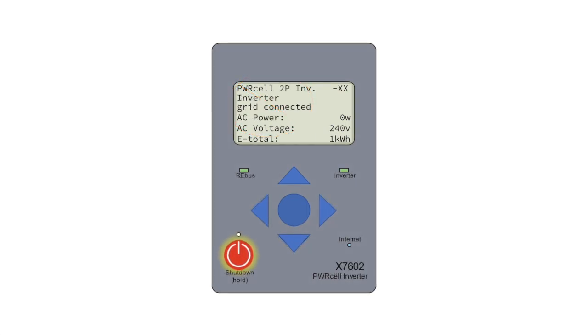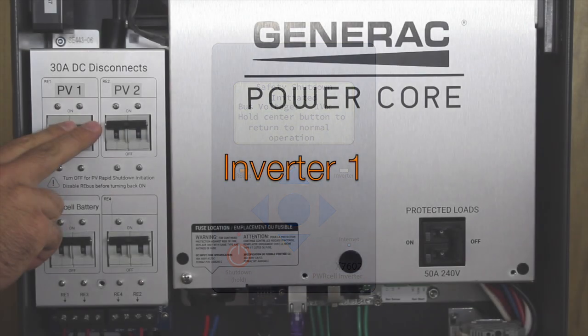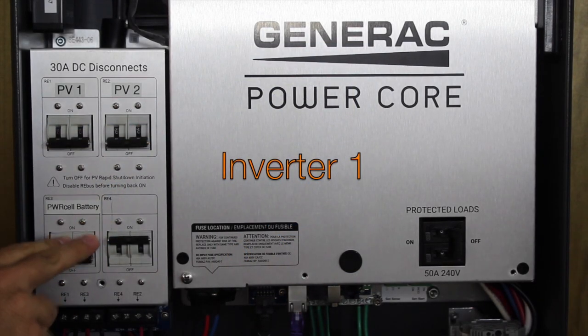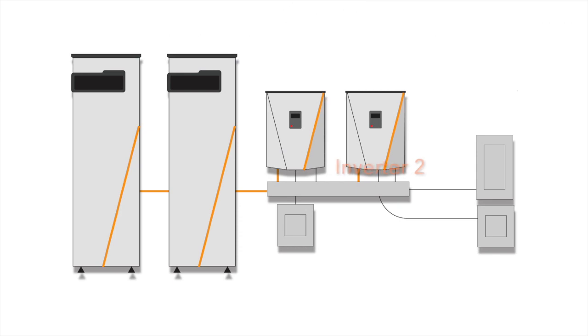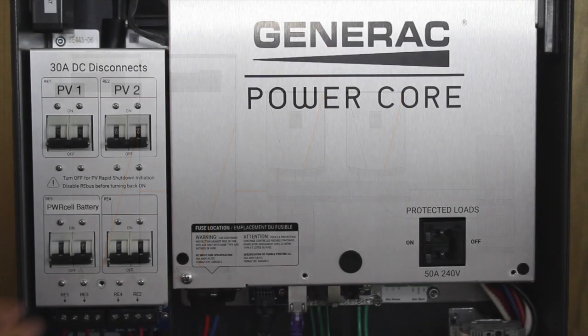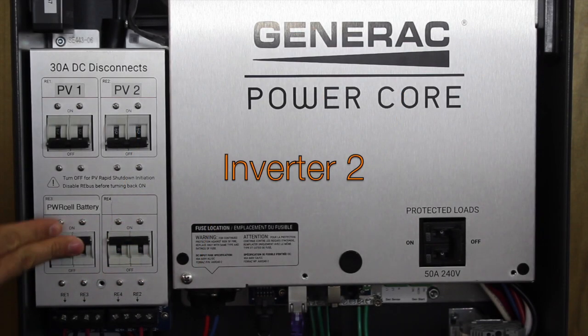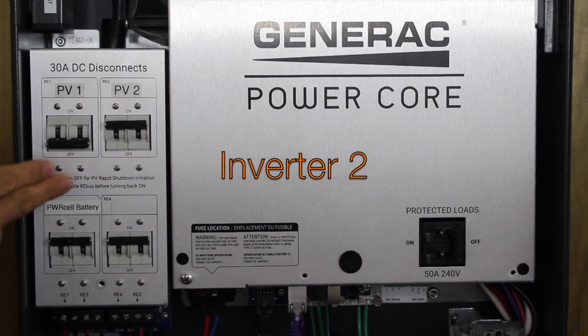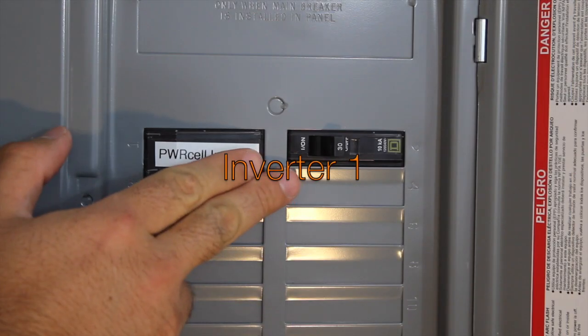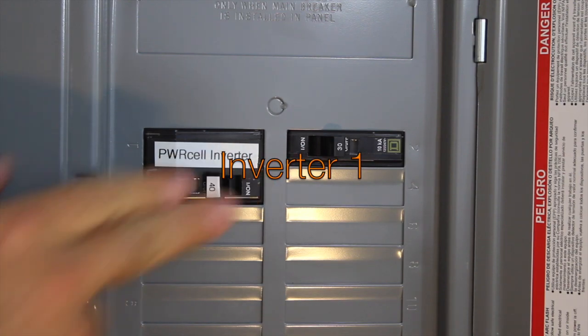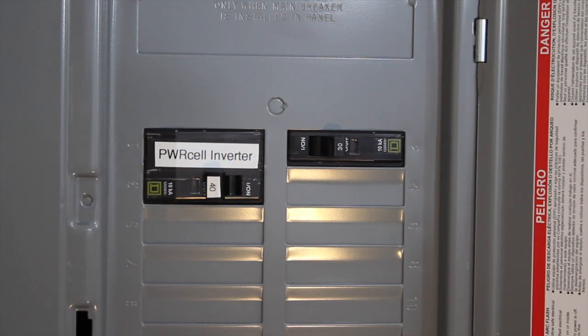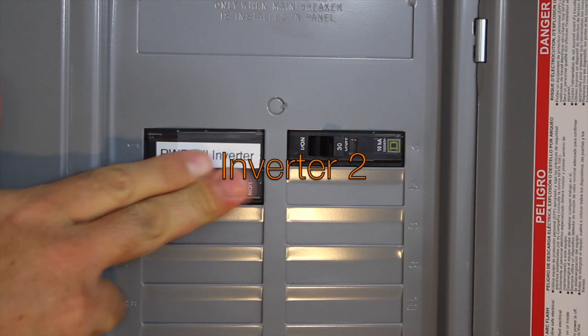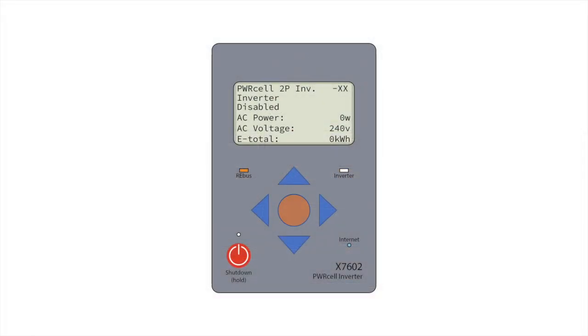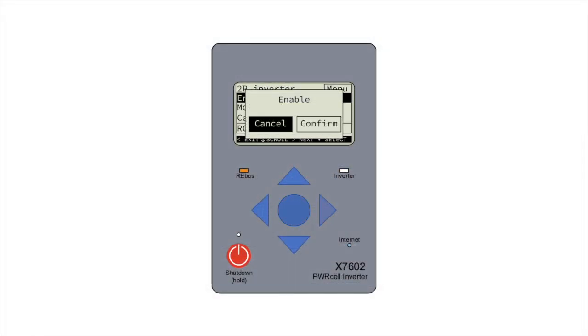Now let's disable inverter number 1 with either the red shutdown button or by selecting disable through the inverter menu. Turn off all PWRcell disconnects on inverter number 1. On inverter number 2, turn on each 30-amp DC PWRcell disconnect connected to rebus devices. De-energize inverter number 1 and ensure the screen goes completely dark. Then energize inverter number 2 and enable the inverter as we did the first time. Ensure it is grid connected.